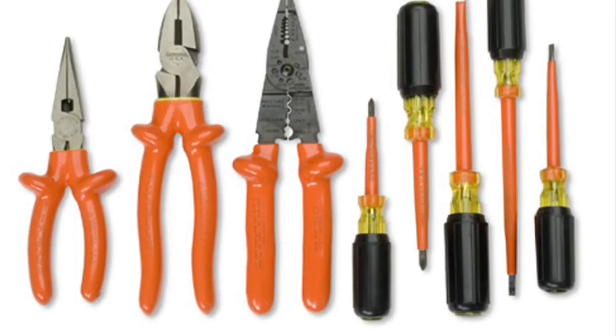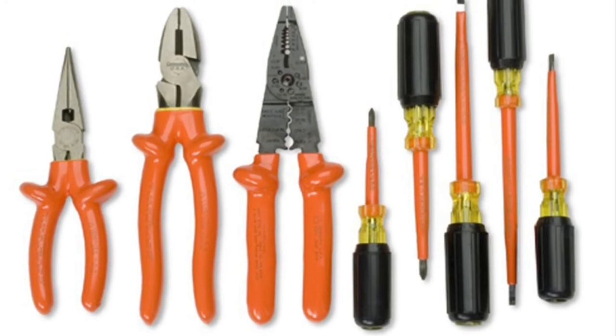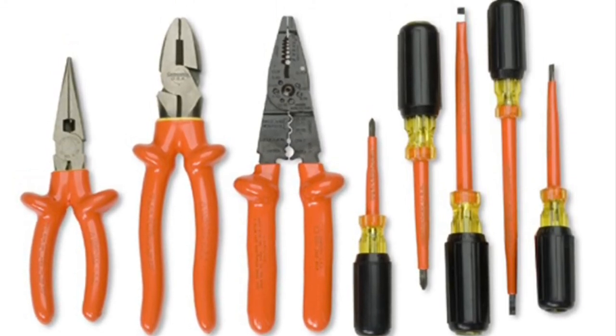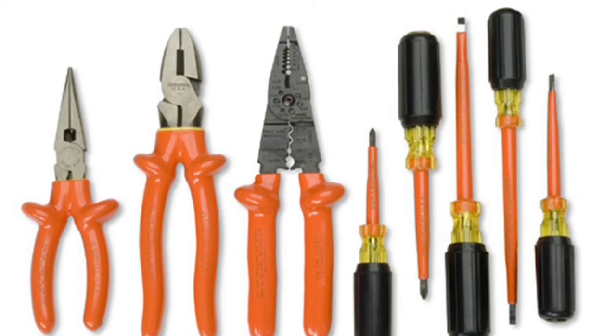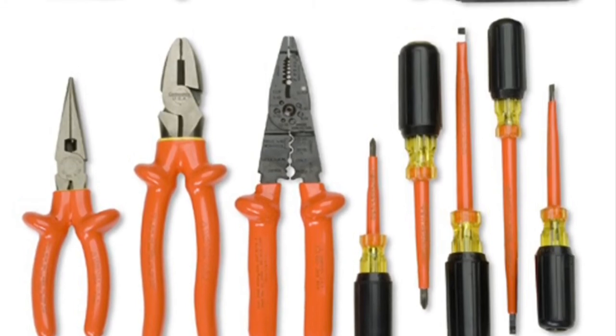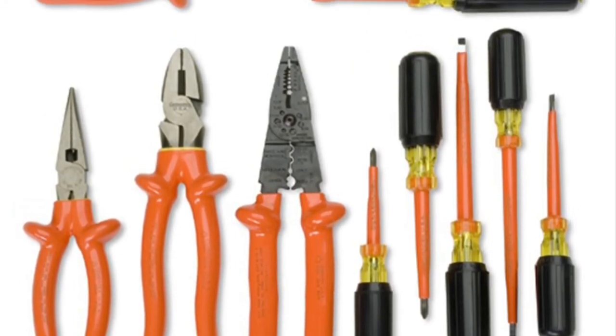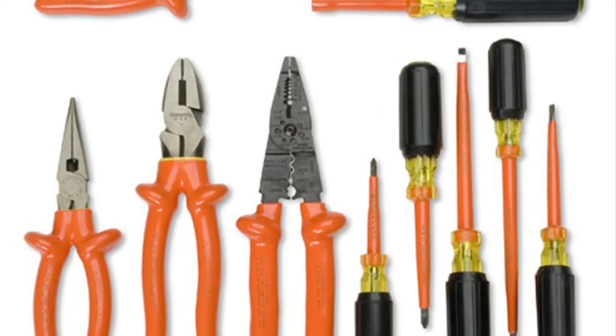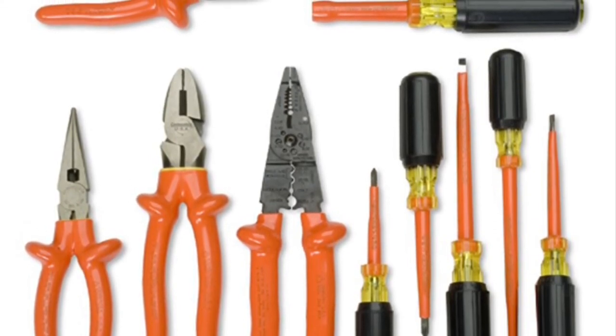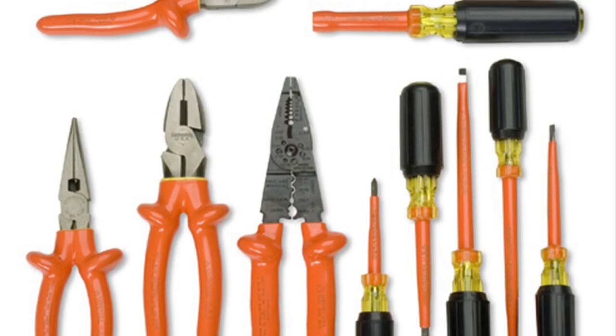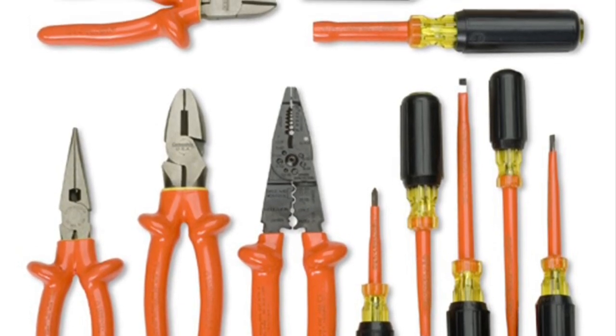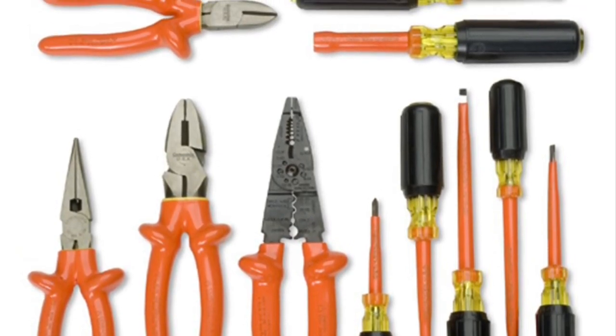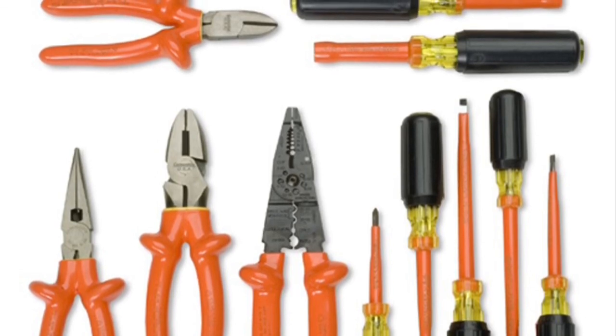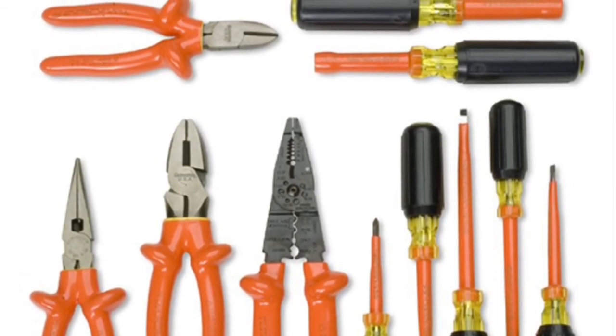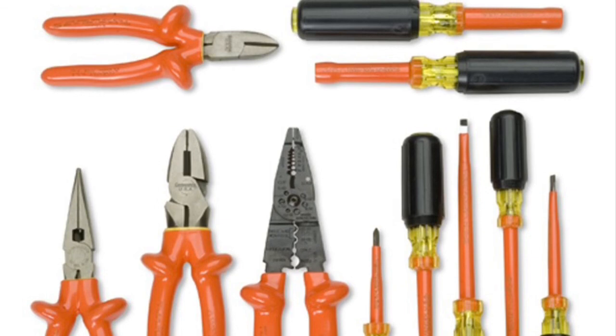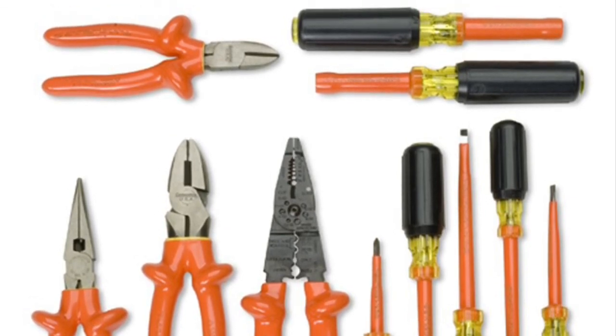Employees shall use insulated tools or handling equipment, or both, when working inside the restricted approach boundary of exposed energized electrical conductors or circuit parts where tools or handling equipment might make unintentional contact. Insulated tools shall be protected from damage to the insulating material. Insulated tools shall be rated for the voltages on which they are used. Insulating tools and equipment shall be inspected prior to each use. The inspection shall look for damage to the insulation or damage that can limit the tool from performing its intended function or could increase the potential for an incident.